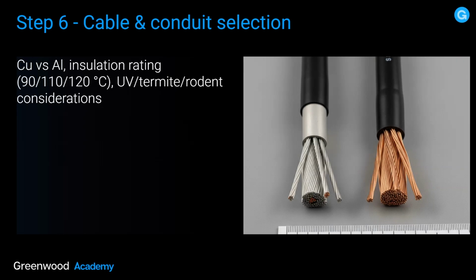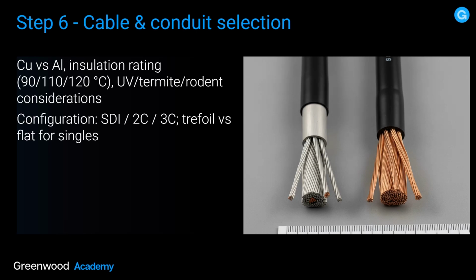Step 6, cable and conduit selection. What we're talking about here is a selection between copper and aluminium, and the qualities of that insulation, both in 90, 110 and 120 degree variations, and also is insulation termite and rodent proof, very, very important in a direct bury configuration. The configuration, is it going to be SDI, 2-core, 3-core, trefoil versus flat for singles? You may be putting in conduit as well. We're not really covering the conduit side of things in this particular presentation, but these are the things you have to work out well before you get to site.